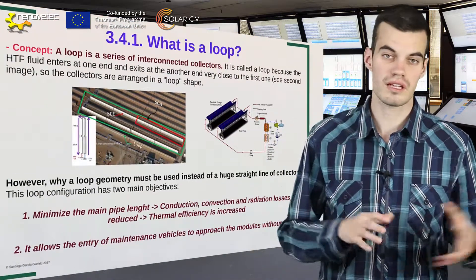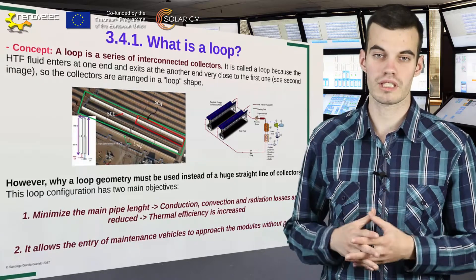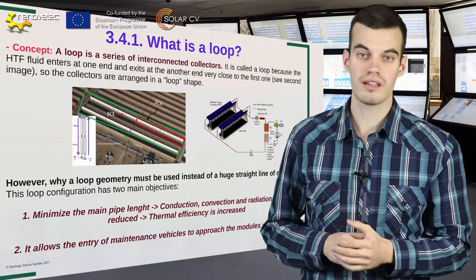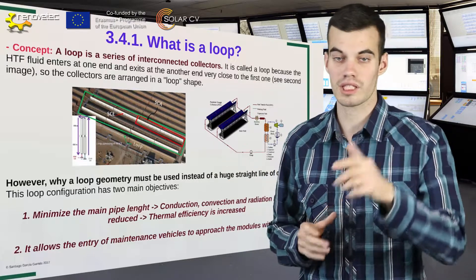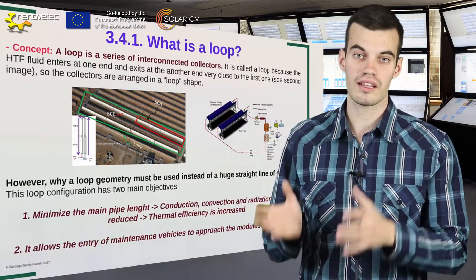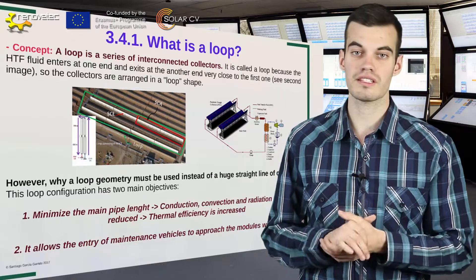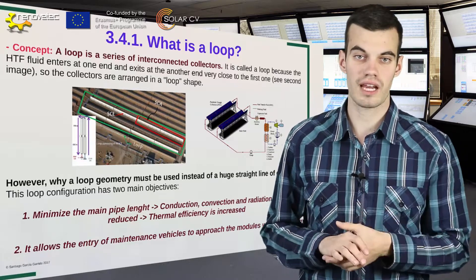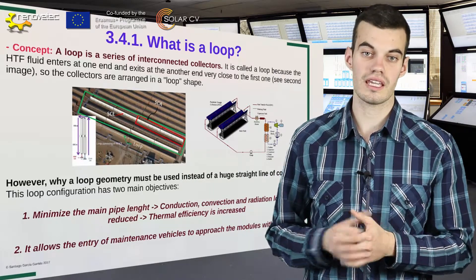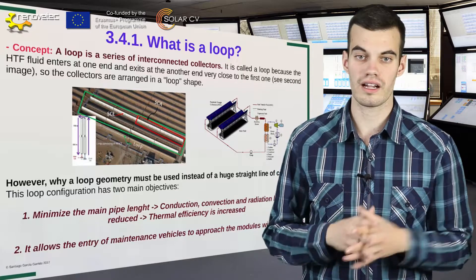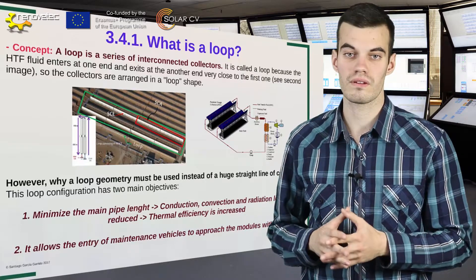The main concept at the beginning is the loop concept. What is a loop? A loop is a series of interconnected collectors. First, we have a module which is responsible to absorb this solar radiation and the reflected mirror must reflect this solar radiation into the absorber tube, and this absorber tube must transform this solar radiation into thermal energy. However, these modules are grouped in collectors. More or less, each collector has from 8 to 12 modules.